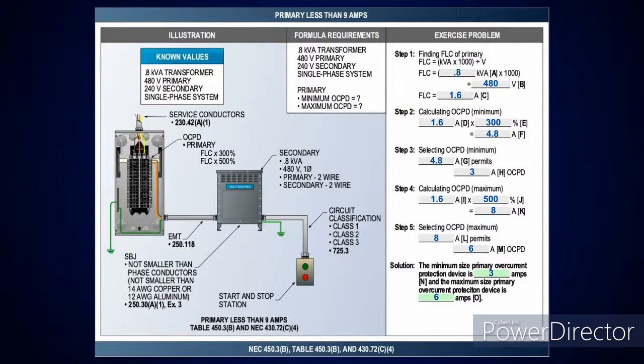Then you look in that table and come across for primary protection only. It's going to say 300%, but there's no superscript 1 above that. So that's 1.6 times 300%, which is 4.8 amps. I look at table 240.6(A), and it tells me the next size below that is a 3 amp overcurrent device.